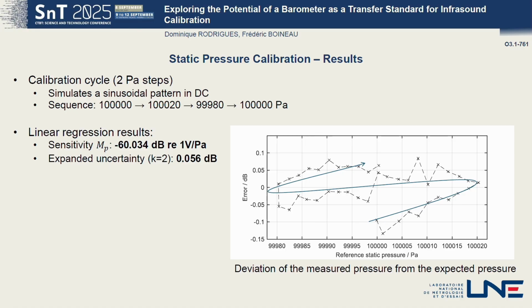So this simulates a sinusoidal pattern, but of course here in DC. This calibration leads, through linear regression, to a sensitivity of minus 60.034 dB with an expanded uncertainty of 0.056 dB in this case.